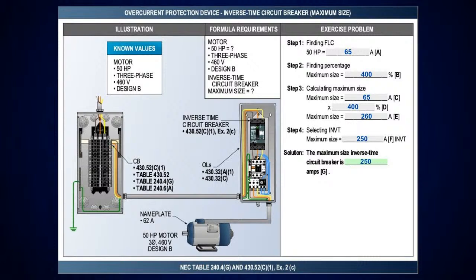Just like I had for that. Now, the only thing you have to look at here, the 400% is where the full load currents are 100 amps or less. If that horsepower motor was greater than 100 amps, you'd take it at 300%. Okay. But this one, it's less than 100. So you just take the 65 amps times 400%, it's 260 amps. The next size below that is what? A 250 amp. Now, that's not hard to follow.